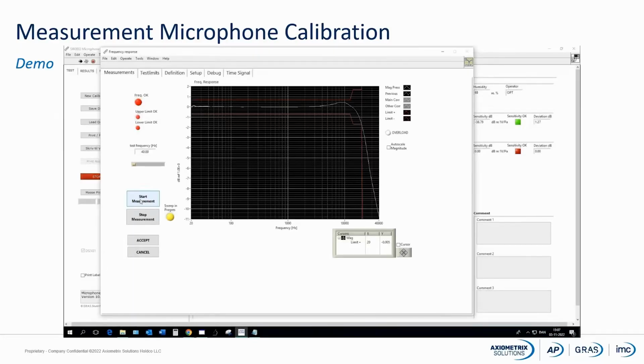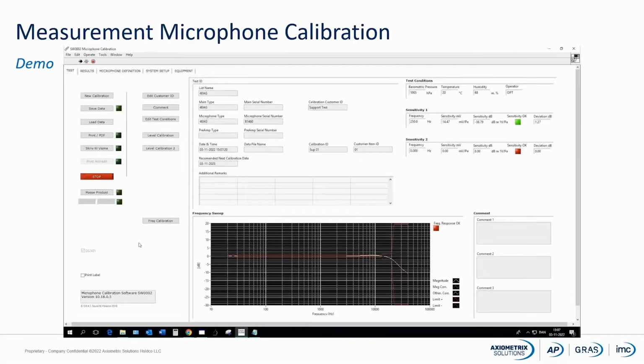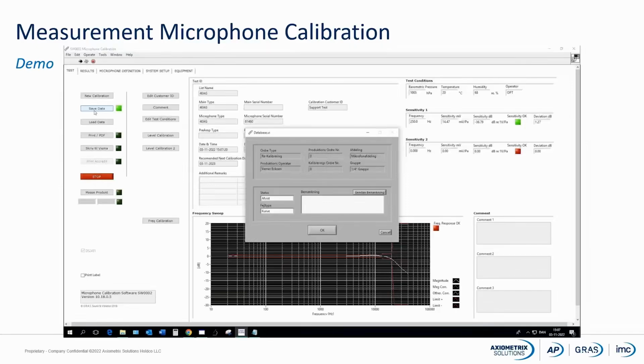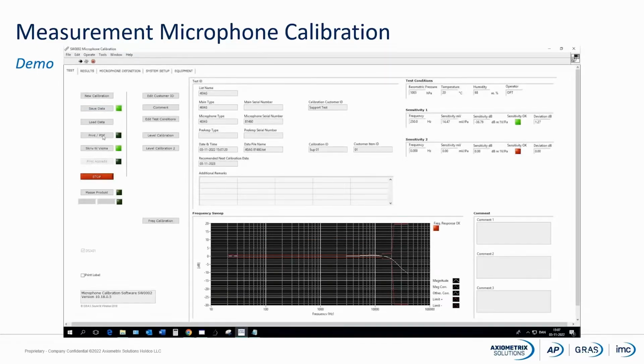And yeah, to be right honest, it's actually due to the microphone I have here, which is my demo microphone. And yeah, it's touching the tolerance, but I will accept it. And if we look now, we did have our sensitivity with a green indication, everything is okay there. But we have also done the frequency response, but it's failed the frequency response. So now I can save my data, and it's what I call the raw data. It's all the measured values, and if I press on the print PDF, then it will actually create a certificate, a nice certificate, and then we can use that.